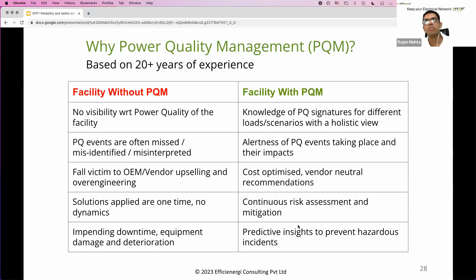And this is a typical strategy to deploy a power quality monitoring, a management strategy, which encompasses not only voltage and current monitoring, but also temperature, humidity, environmental parameters, along with it, DC voltages for batteries. This is typically for a photovoltaic grid, but it can provide all of these benefits, whether the sag or swell is coming from outside or within my facility.